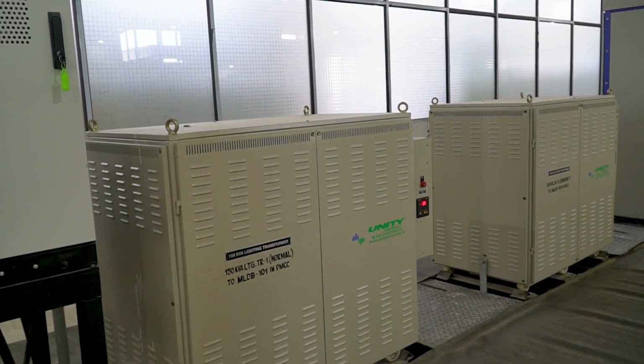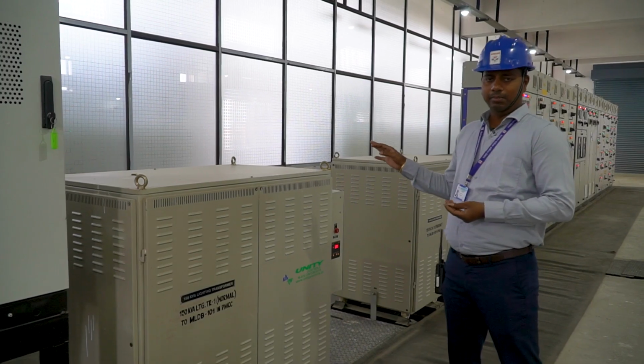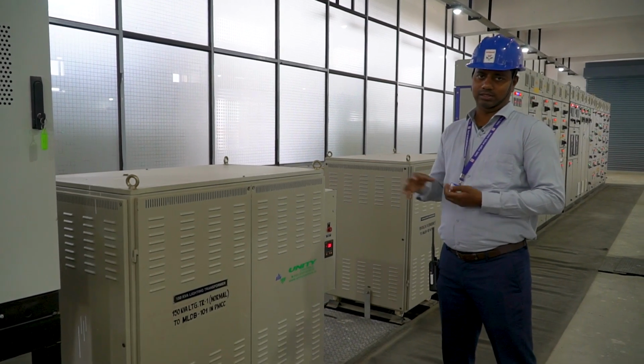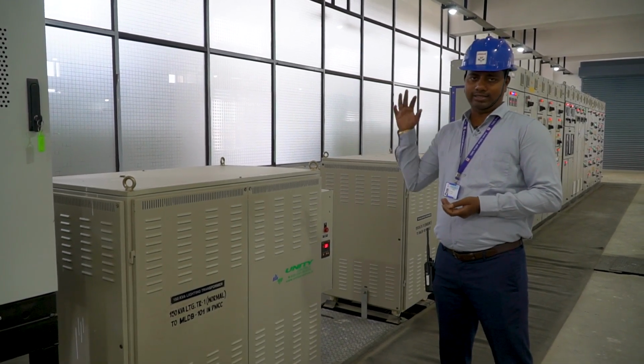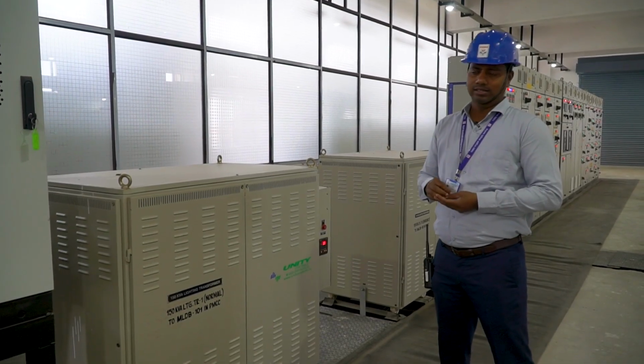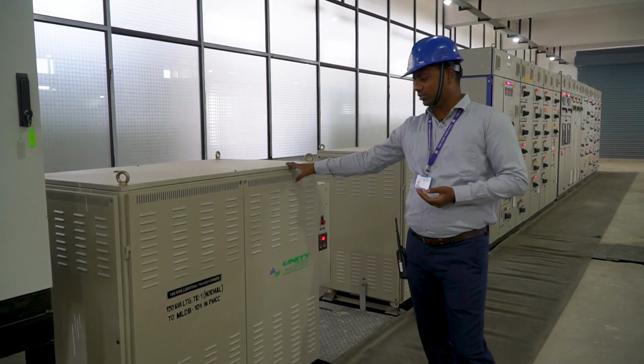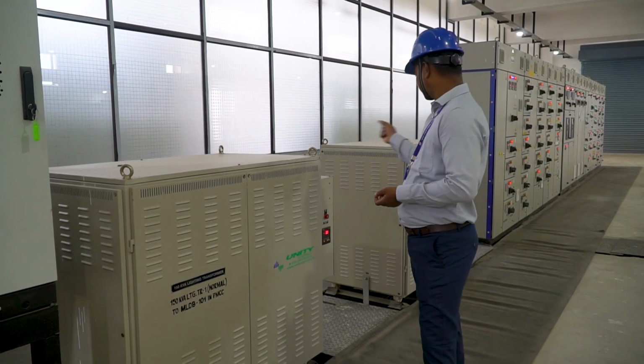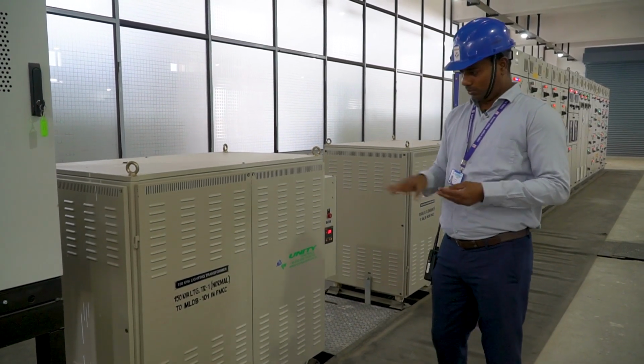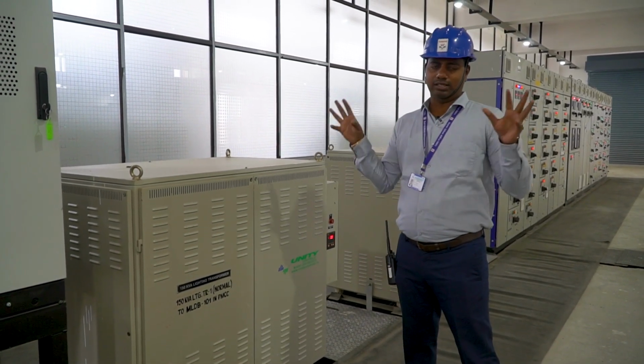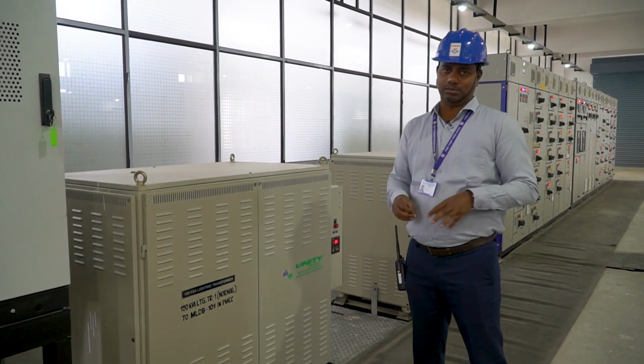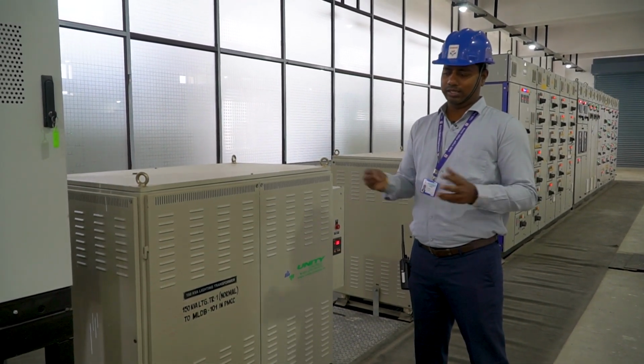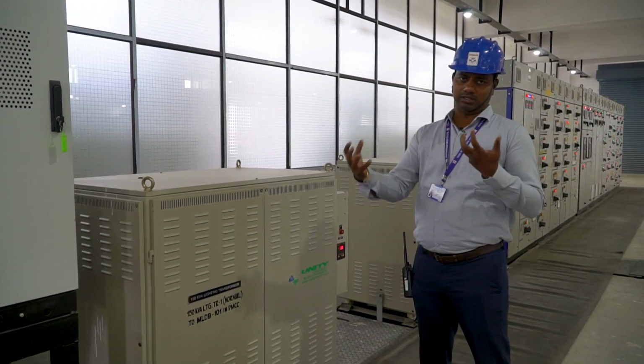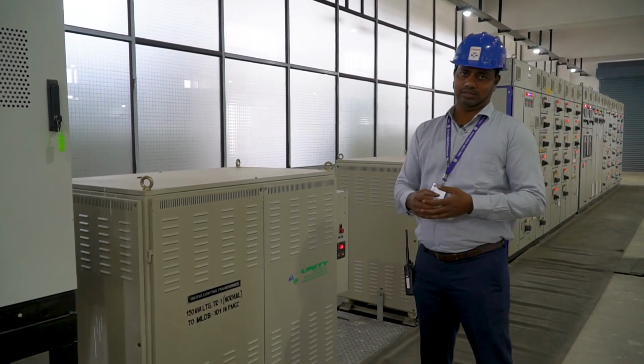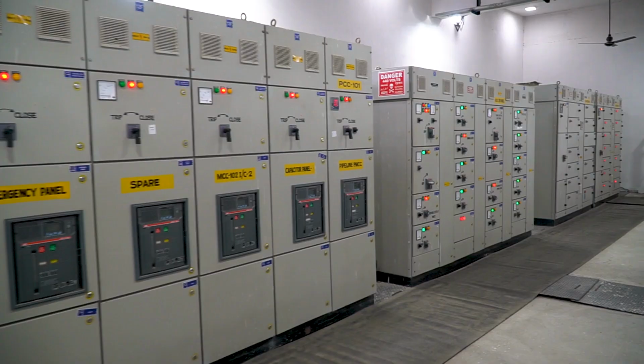These are two lighting transformers meant only for lighting loads. This will protect the lights from surges. This lighting transformer is connected to the MLDB, which is connected to the EMLDB. The purpose of this panel is to protect the lights available inside the terminal or any plant, so that no light is affected because of fluctuation in the voltage. That is the purpose of these panels.